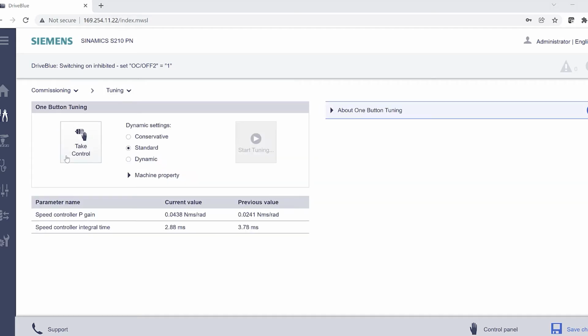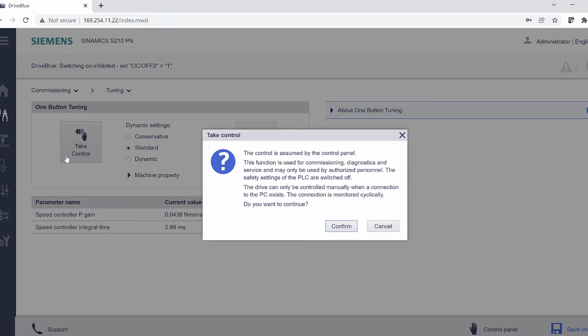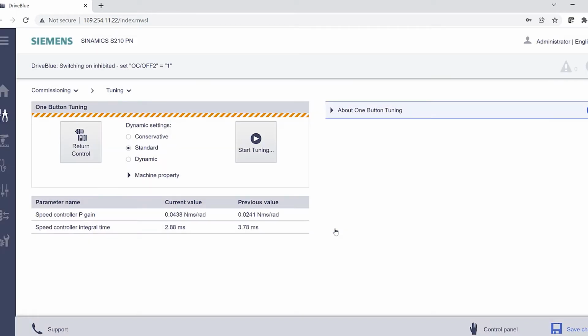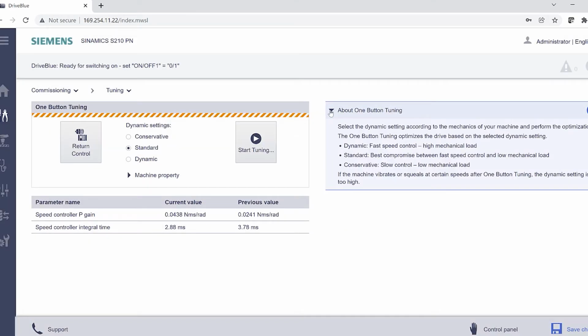When you select Take Control, a warning will pop up letting you know that, as a safety precaution, if the PC and S210 lose communication for too long, the connection will be canceled and you will need to reconnect. Note that there is a drop-down on the right of this page, which provides details for the different types of tunes that can be performed. For this example, we will perform a dynamic tune.